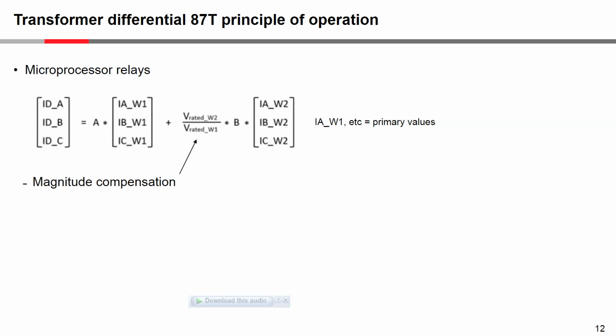So as I said, this voltage ratio is really your magnitude compensation, and that is what converts the winding 2 current level to a winding 1 current level. Because if you're going to sum two values, you have to bring them to some common level. For a transformer, normally current goes in on the high side and comes out on the low side, and for a perfectly balanced load flow, those currents are not going to have the same magnitude. So if you want to sum them, you need to convert one of the currents to be equivalent in magnitude to the other.